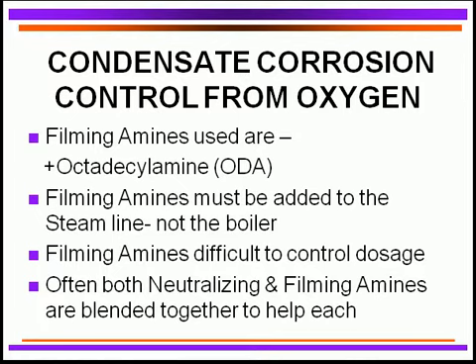However, people have been using a combination of neutralizing and filming amines together. When used together, they complement each other and do a much better job of providing protection against both carbon dioxide corrosion and oxygen corrosion.